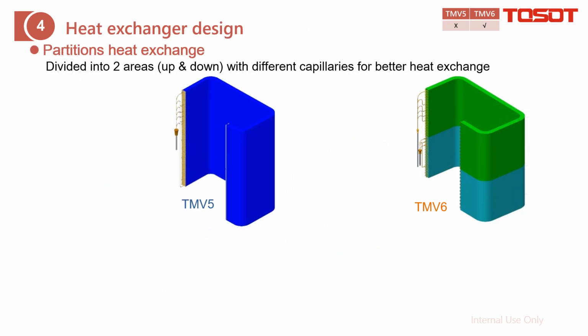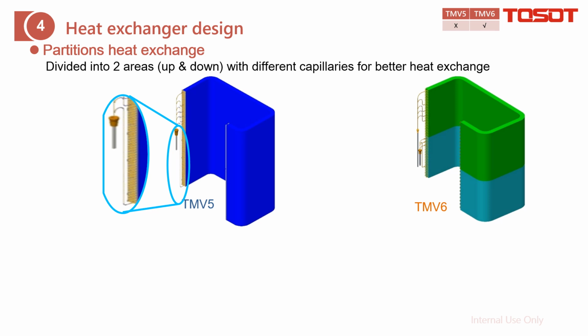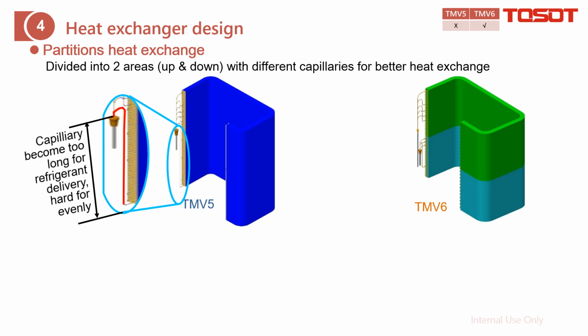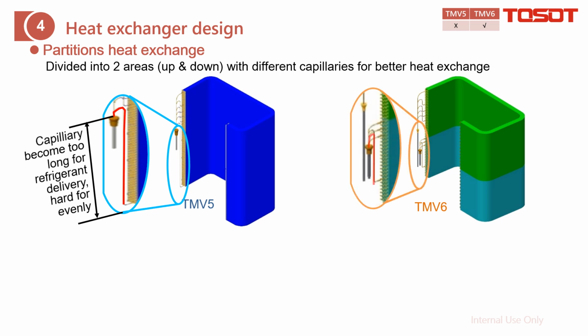Heat exchanger design. First is the partition setting. For TMV6, compared with TMV5, we make the outdoor heat exchanger divided into two partitions, up and down. First, let's focus on the TMV5, which is here. We apply this distributor to distribute the refrigerant into different passes. However, this is a little bit too long, this is actually the capillary, and if it's too long, for mass production we cannot ensure the refrigerant can divide evenly into different passes, just because it is not that easy to control. As for the TMV6, even though we apply this distributor, this length is only half of that, so the control becomes much easier.